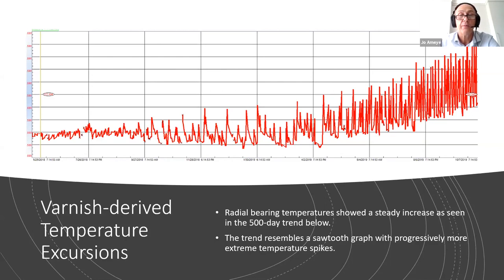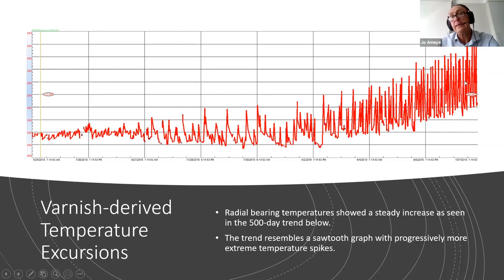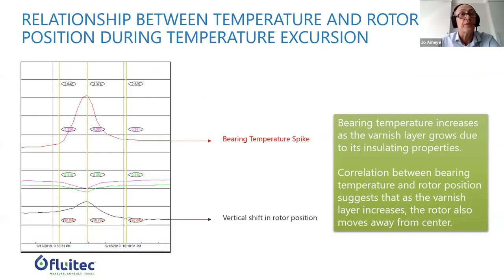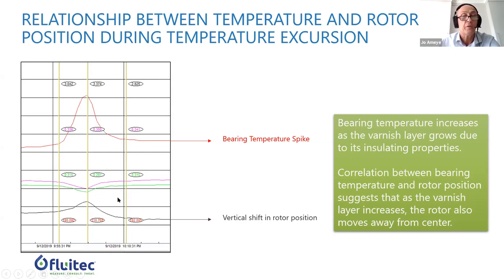Here is another good example showing a 500-day trend. You can again recognize these peak increases over time, and if you draw a regression line you can see the increase occurring. You also see this sawtooth graph, and we often receive the question: why is this typical? Can we explain this sawtooth graph with these progressively more extreme temperature spikes? Yes — to understand that, we need to combine the temperature relationship together with the position of the rotor.